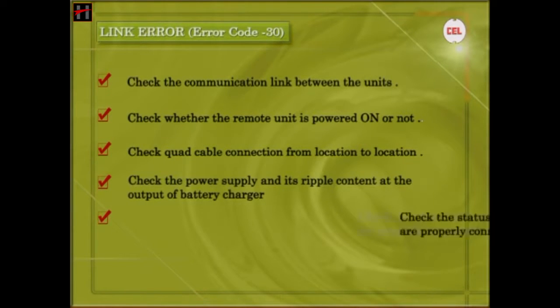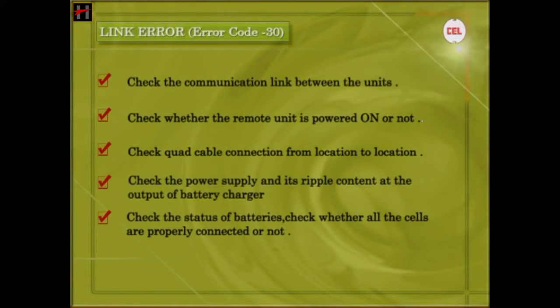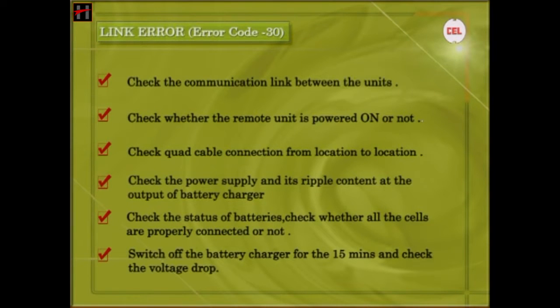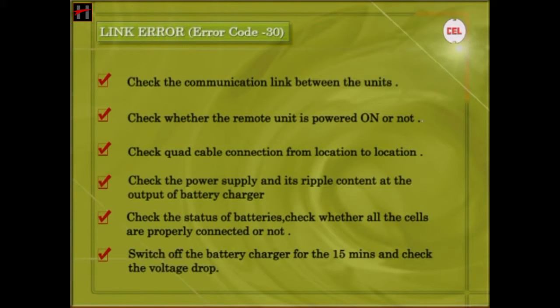5. Check the status of batteries and check whether all the cells are properly connected or not. 6. Switch off the battery charger for 15 minutes and check the voltage drop.